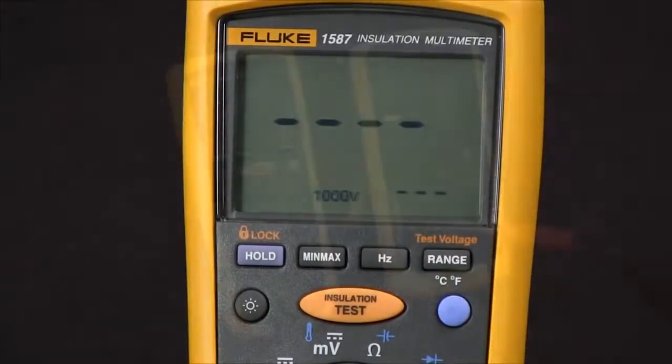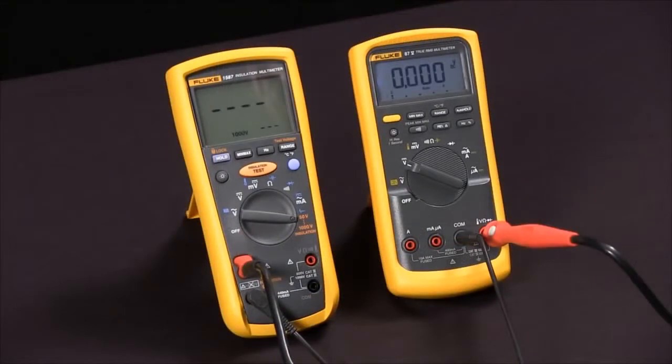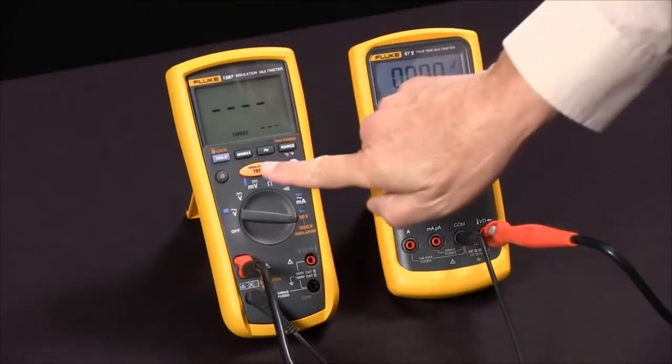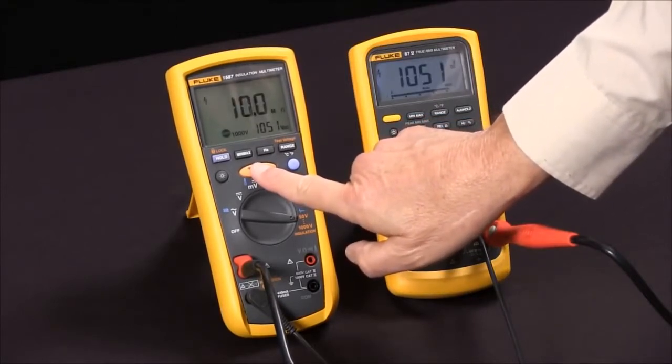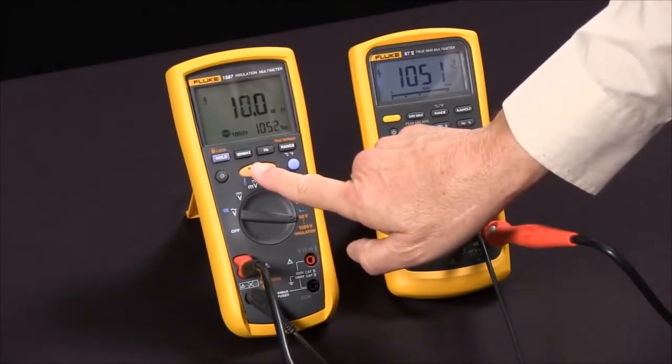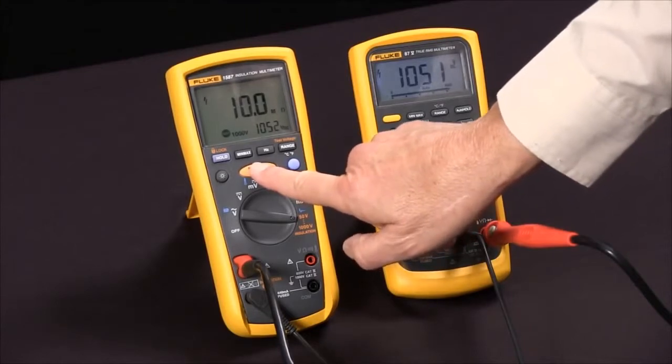I'm going to use 1,000 volts, and now we're ready to do our test. I'll press the test button, and you'll see it apply, in this case 1,052 volts, and read 10.0 megaohms.